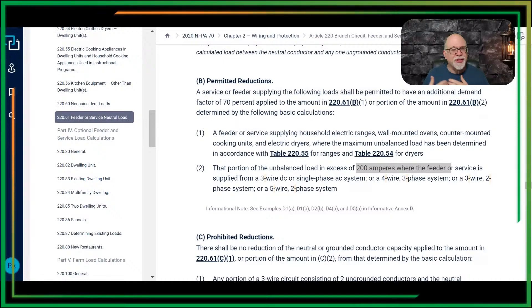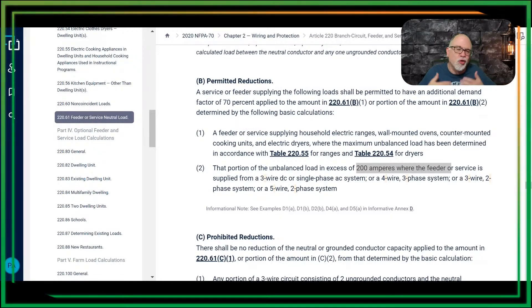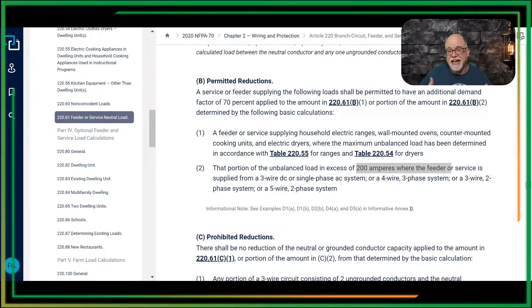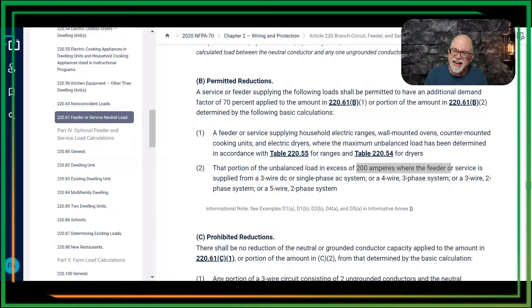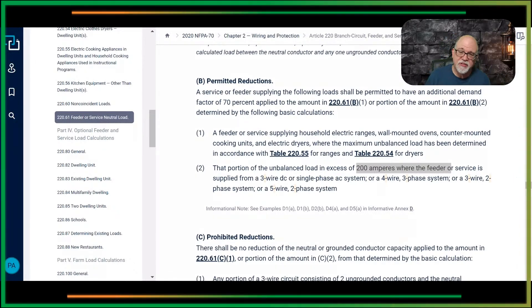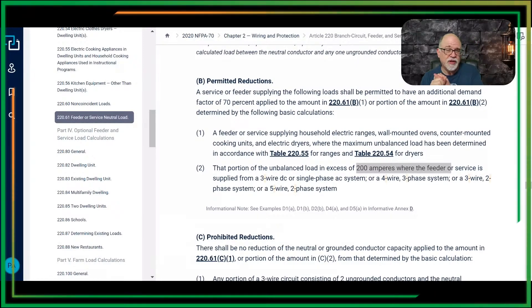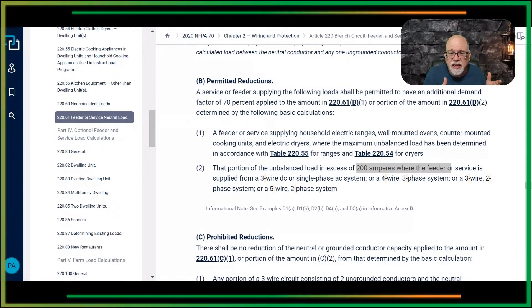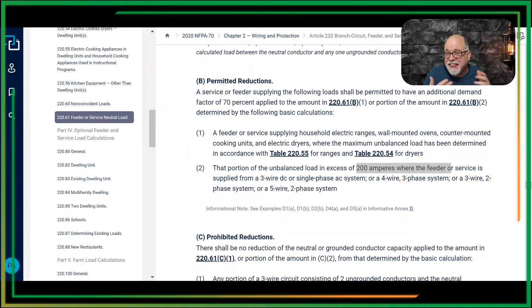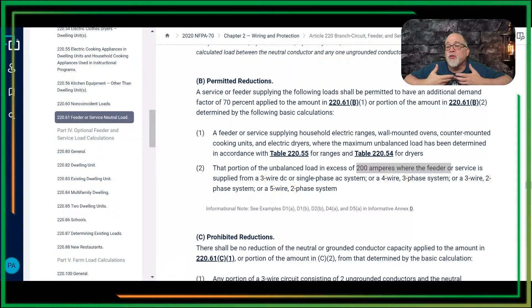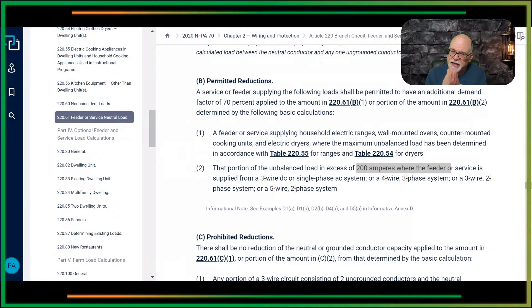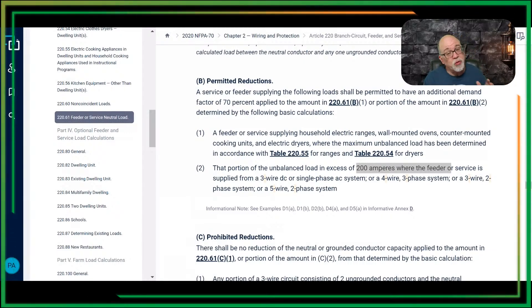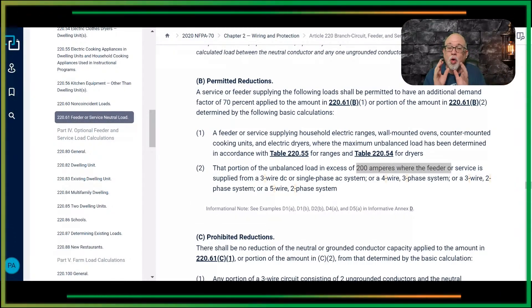In the real world, chances are with a dwelling you're never going to apply B2, because the neutral contribution probably never reaches over 200 amps unless you have a huge mansion. Most of the time it's not a factor — this is why people don't pay attention to it. But if I'm writing you an exam question, I might focus on you applying 70% to the cooking appliances and clothes dryer, and then have an overall neutral load over 200 amps. If you don't notice that OR and apply both, that would be wrong under the 2020 and 2017 editions.